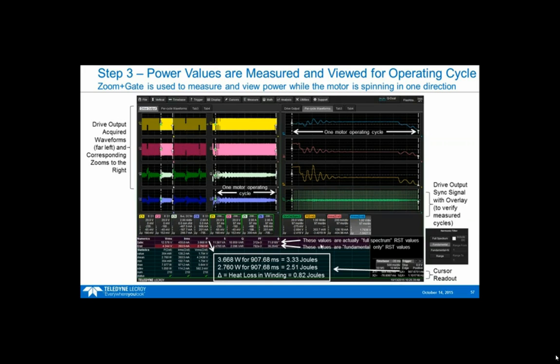This user was very, very clever. He set up the drive input, what we'd call the ABC, to be unfiltered, meaning it's looking at the full spectrum of the power. Then the RST, the drive output setup, is set to look only at the fundamental. So you can see the power level for the fundamental is quite a bit lower by a watt than the power level of the full spectrum, and the difference is the heat lost in the winding. He's able to calculate that as well. Pretty clever application of this tool.